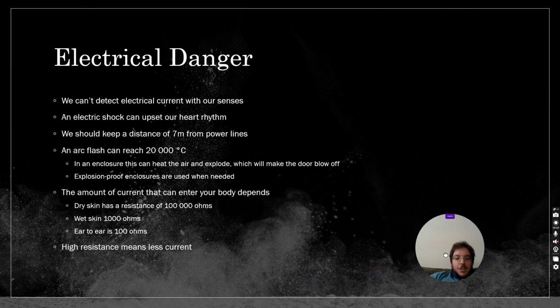So why is electricity so bad? Because we can't see electrical current, we can't hear it. Well, you can if it's really bad, but typically you can't hear it, you can't taste it. So that's why we want to stay 7 meters from electrical lines if possible. An arc flash can reach 20,000 degrees, and in an enclosure it will heat the air to the point where it can blow the door right off.